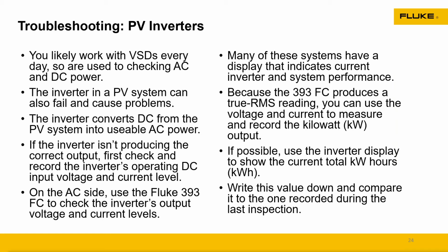We want to make sure that on the inverter side, the load is correct and that the balance of voltage and current coming out of it is correct as well. That's where we're going to be using a multitude of those products like the thermal imager, the clamp meter, the DMM, to do all this troubleshooting. This is where we can go in and validate that what we're seeing from the combiner box is the same voltage. You will get a little bit of voltage drop and loss from the combiner box to the inverter, but it shouldn't be a lot.